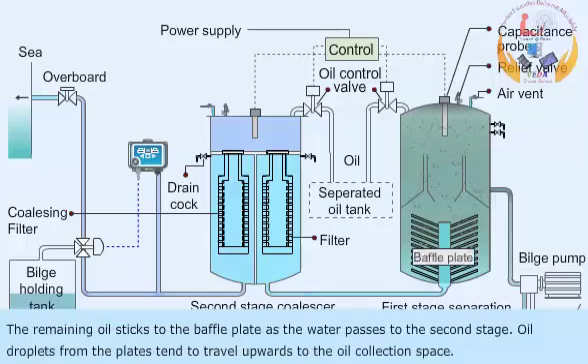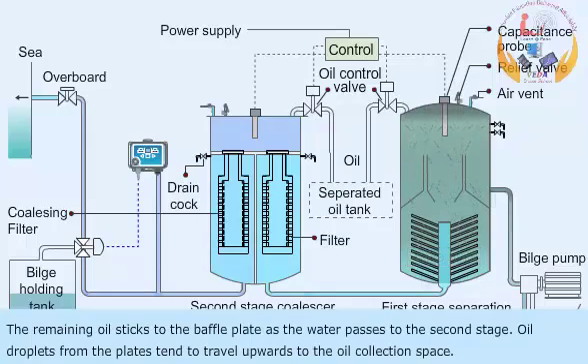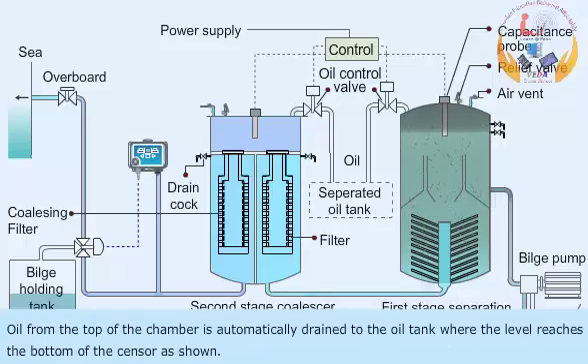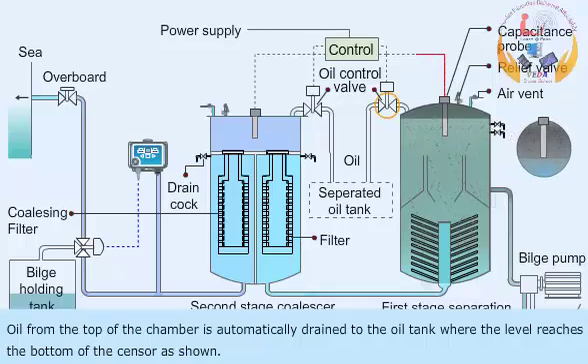The remaining oil sticks to the baffle plates as the water passes to the second stage. Oil droplets from the plates tend to travel upwards to the oil collection space. Oil from the top of the chamber is automatically drained to the oil tank when the level reaches the bottom of the sensor.